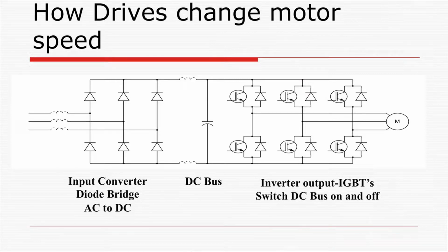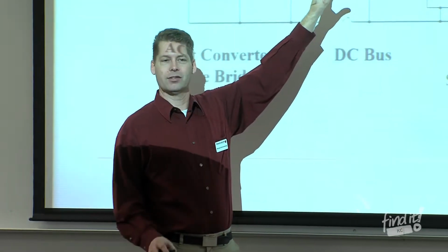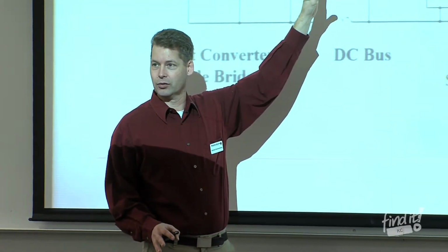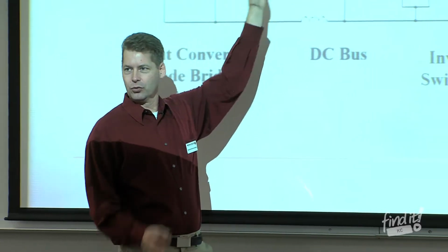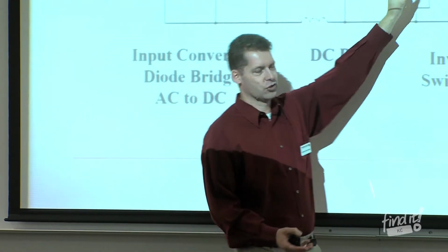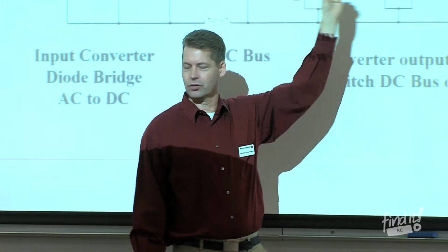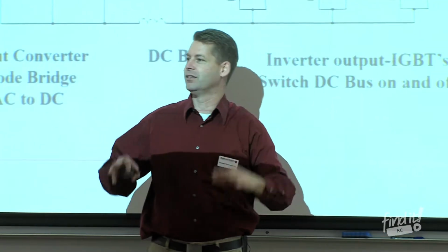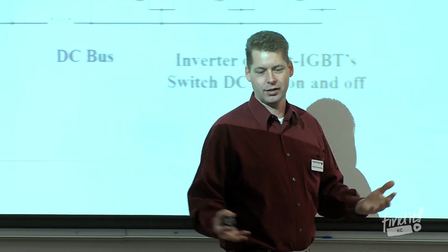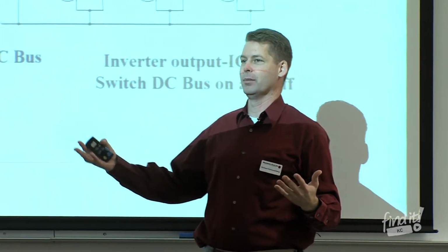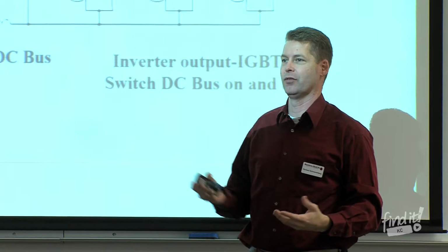So these 3 sections of the drive take AC power coming in on this 3-phase incoming power, 208, 460. We run it through this input converter, these diodes that take all that energy and store it in a big DC bus inside the drive. Now on a 480 volt system, that's 650 volts DC stored inside the drive. So you've got this big DC energy source, and then we have to chop it up on and off and on and off with these transistors and send power out to the motor in a chopped up DC form that, when the motor gets it, approximates a sine wave. So it approximates the power that the motor was expecting to see in a sine wave fashion anyway.